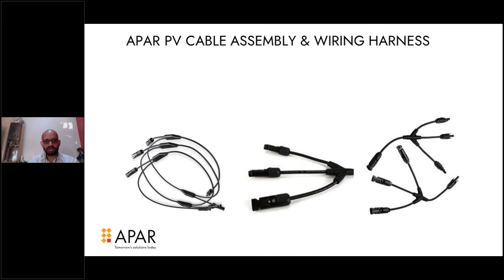And the advantage of using this solar harness is that 30% of the electrical contractors' cost is in installing the string and array cables, and the time needed for installation can be saved if you use the solar harness. Again, if you use these Apar solar harnesses, 30% of your cable consumption is also saved compared to direct cable installation. And it's a common trend that 10% of the cable gets scrapped during direct installation. If you're using the pre-built solar harness, that saves the cost also.